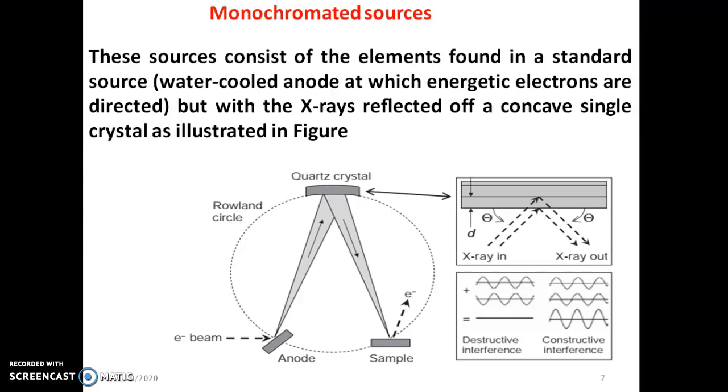And this quartz crystal, when the X-ray from the X-ray tube falls on the quartz crystal, depending upon the Bragg's conditions, the rays are either coming out or get suppressed. So a particular wavelength, depending upon the geometry of anode and quartz crystal, the particular theta and particular wavelength X-rays are emitted out and other wavelengths get suppressed by the destructive and constructive interference condition.